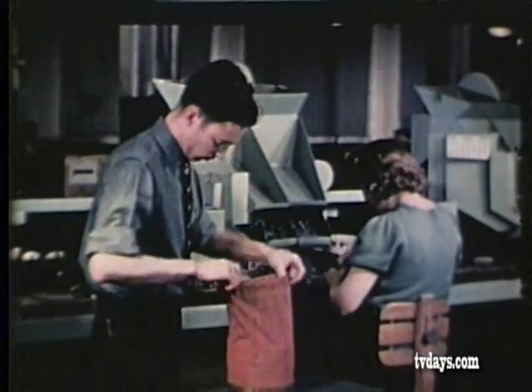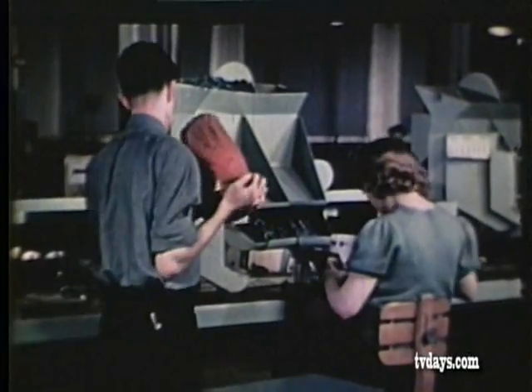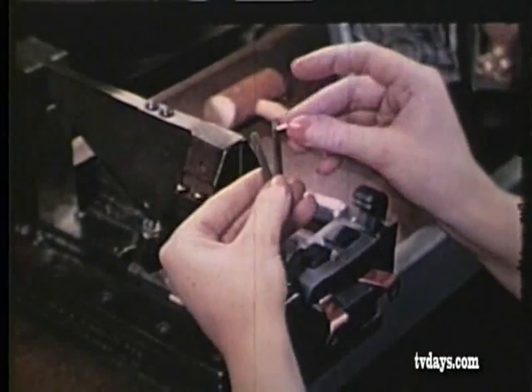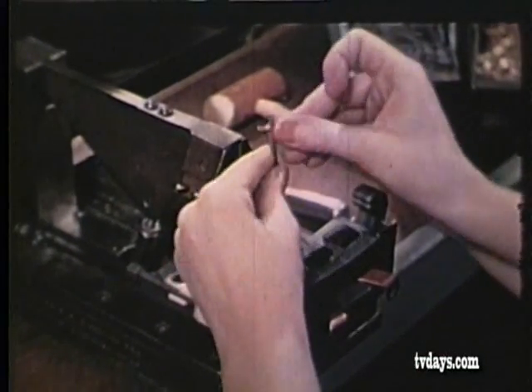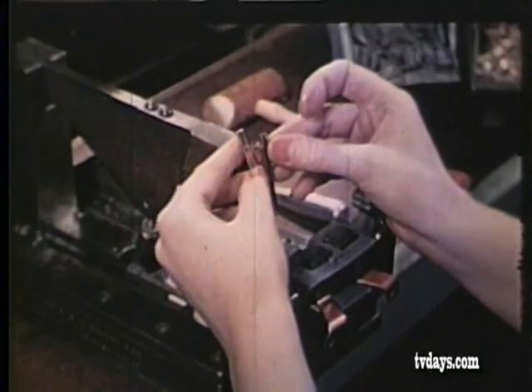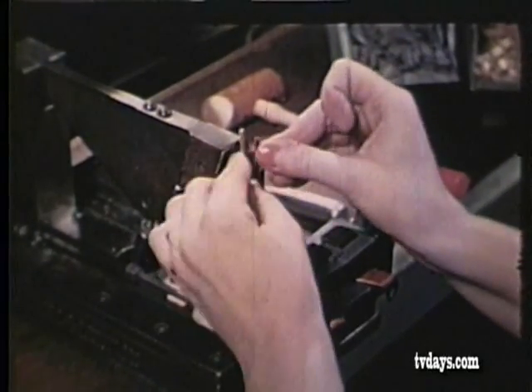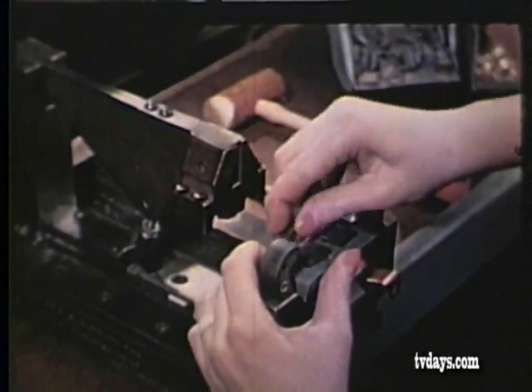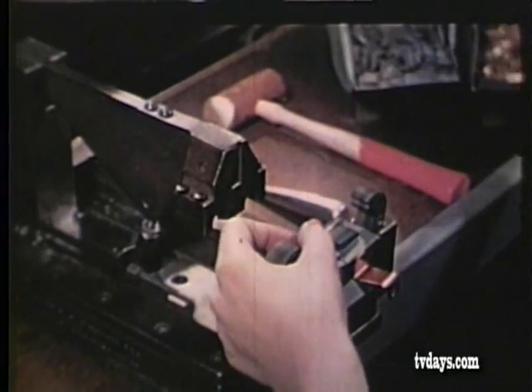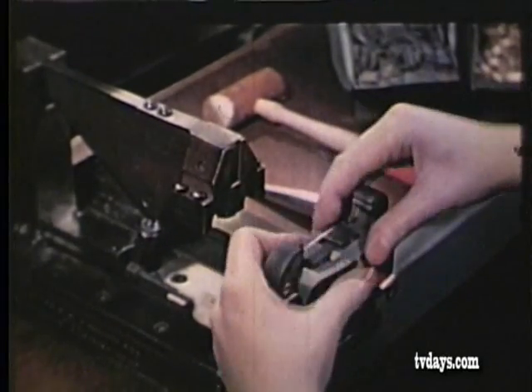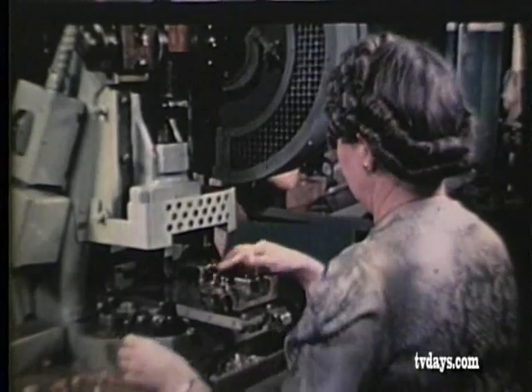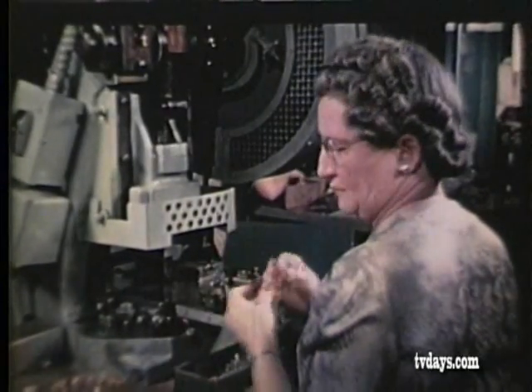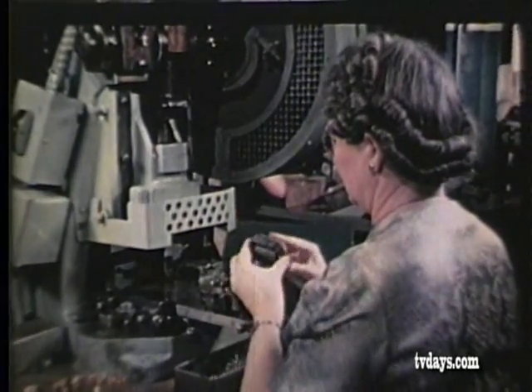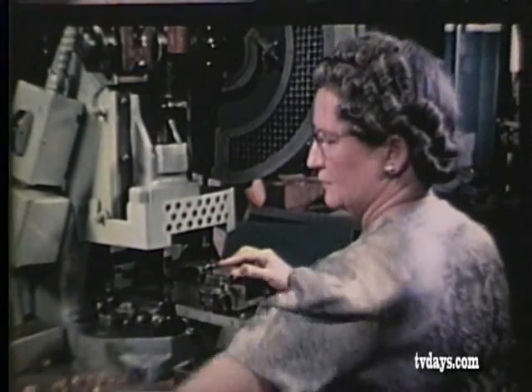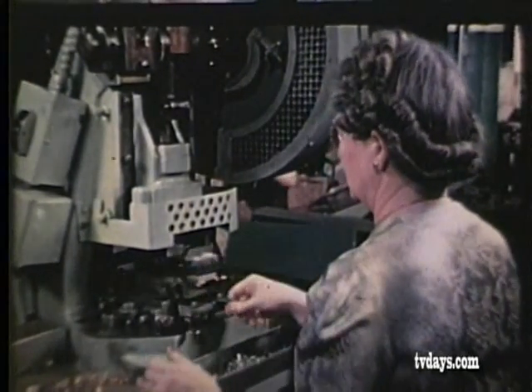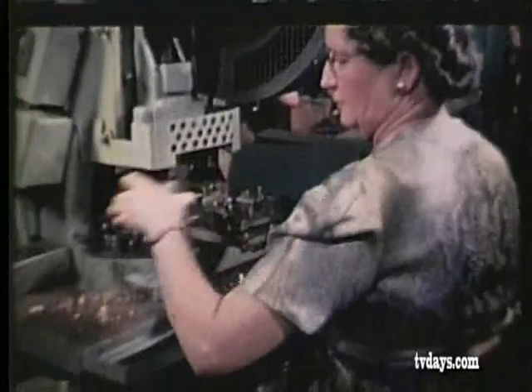We'll have to have a closer look to see the wide limit load shunt which the lab man brought in the sealed bag. Two pieces and a spacer constitute the shunt. It is simple looking, but it assures accurate performance at both light and heavy loads. Each shunt is carefully prepared in the laboratory before it is brought to the element assembly line. Then further down the line we see the riveting of the current coil laminations to the potential laminations. They fit together so closely that the magnetic flux between them is practically unimpeded.